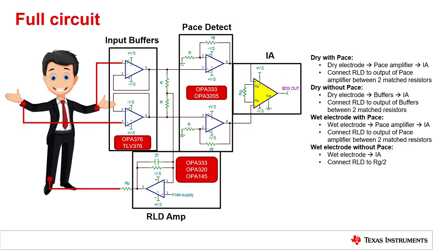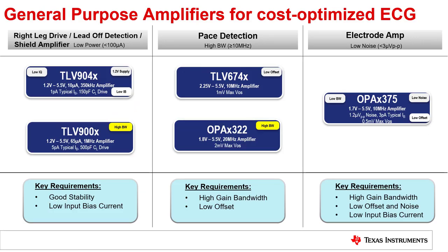The general purpose amplifiers from TI offer the most cost-effective and small size amplifiers in the industry. This slide shows recommended devices for cost-optimized ECG applications. For RLD amplifier applications, the gain bandwidth requirement is not high, but the amplifier may have to drive a high capacitance load. To meet this requirement and save power, low power amplifiers like TLV904X and TLV900X could be a good fit. The TLV904X with 1.2 volt minimum supply and low quiescent current not only helps future-proof your design for a small battery voltage, but also saves valuable battery power.